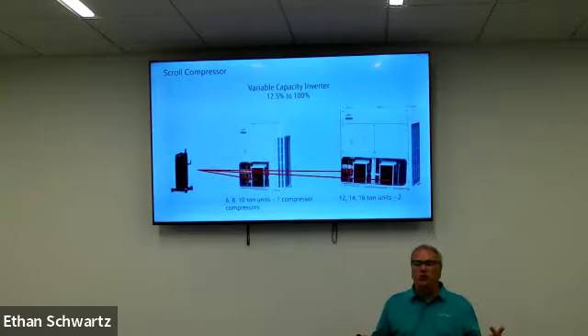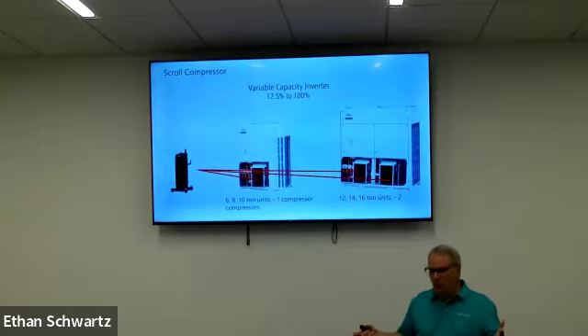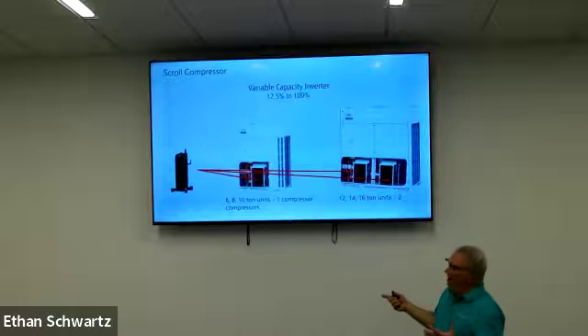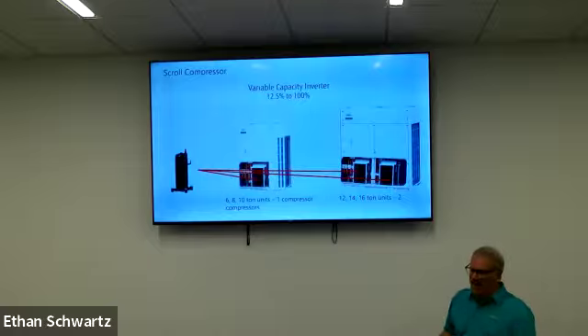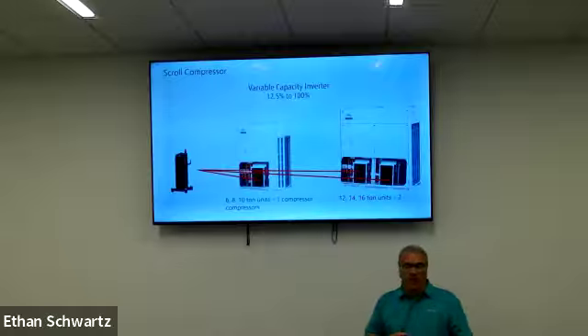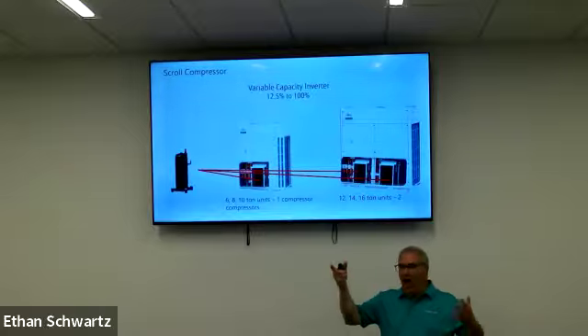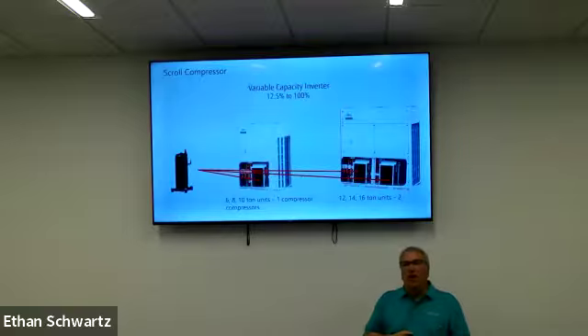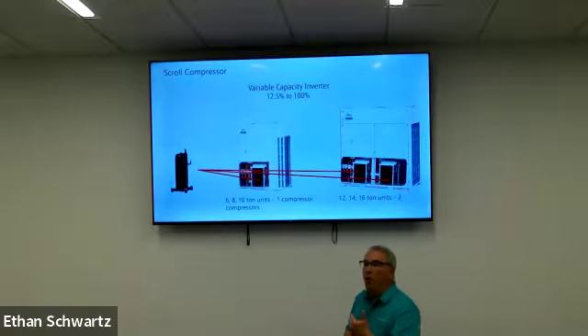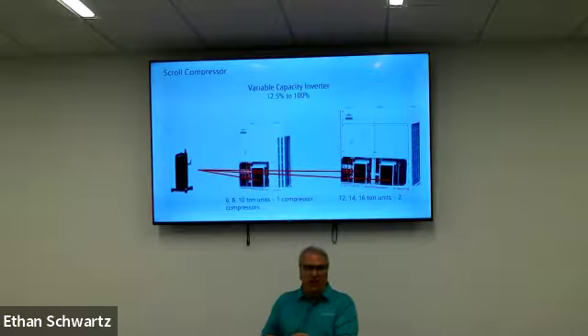So if you have a larger building or larger structure and you're wondering, all right, how should that be broken out? Let's say that the building is 48 tons. You could do 6 8s, 8 6s. You want to do something, could be heat recovery and heat pump. You could do 4 12s, 3 16s. However you think you're going to patch that up, remembering that the more outdoor units that you have, the higher the cost is going to be.